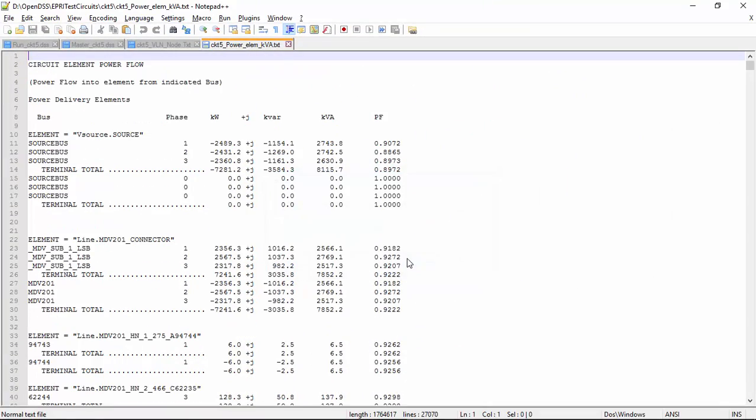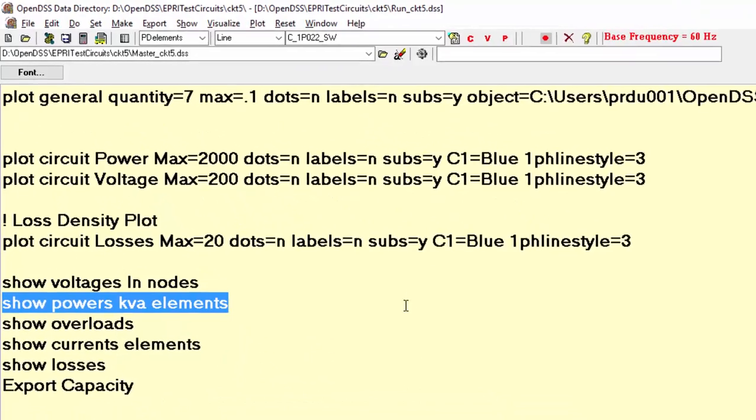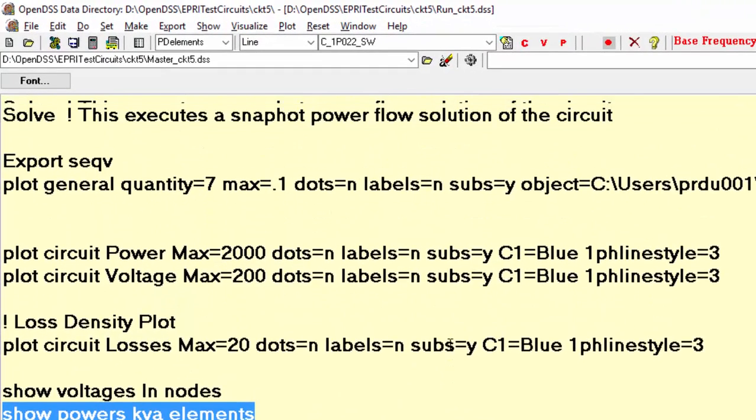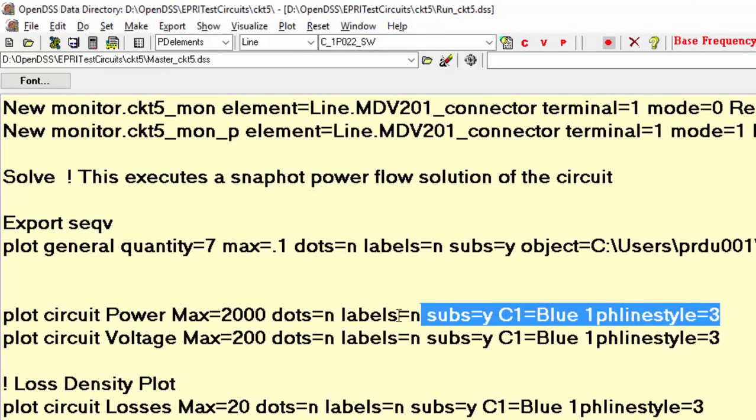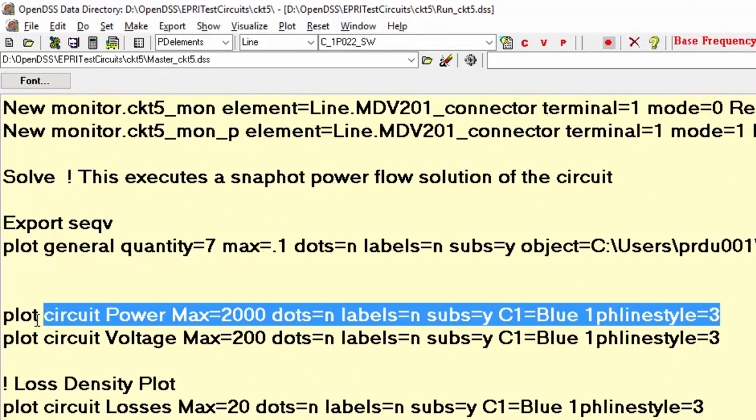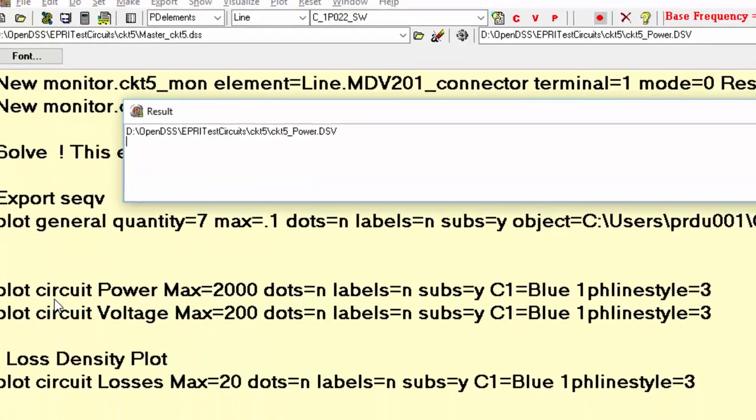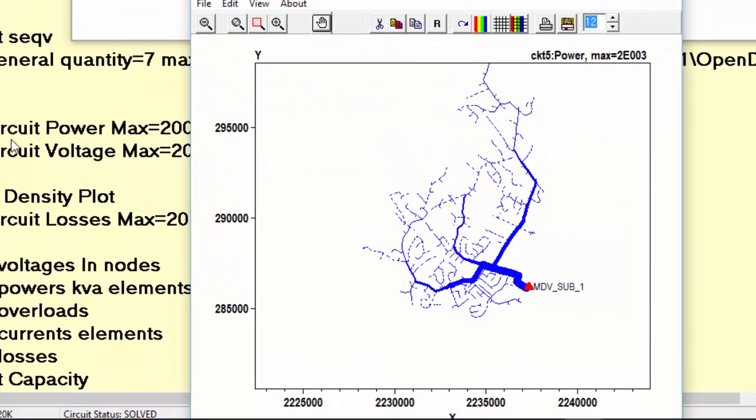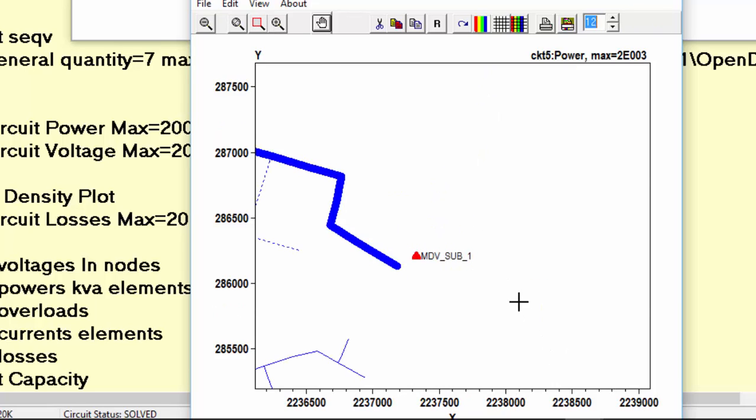For instance, we can use this command line and plot the circuit. In this plot, the red mark represents the substation transformer. Do you remember that it had its sub property set to yes? Here it is. The thicker the line is, the more is the power flowing through it. We can also zoom in and click on any line in order to get some of its results.